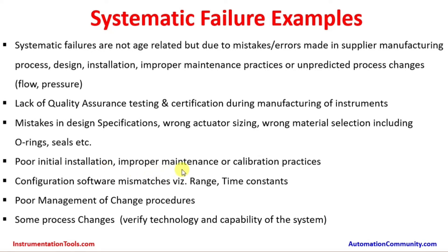Poor initial installation, improper maintenance or calibration practices, configuration or software mismatches such as incorrect range or time constants, and poor management of change procedures are also systematic failure causes. Operations teams focused on increasing productivity or quality may not give sufficient attention to instruments and equipment across the plant. Any process changes must verify the technology and capability of the system, as neglecting this can lead to failures at rare but significant chances.